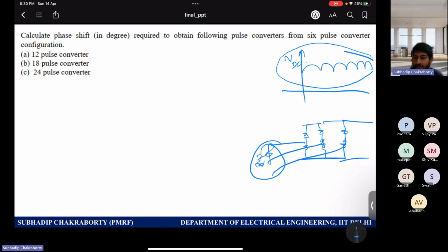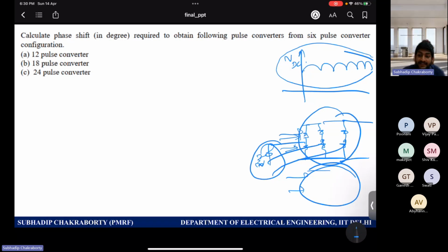So to improve the current quality at the AC side as well, if you use multiple such devices with some phase shift, you can tactfully cancel the harmonics. By Kirchhoff's current rule, some current harmonics may be rejected here and some there, by providing some phase shift arrangement. If you add those currents connected in parallel, your current quality will be more improved and closer to sinusoidal. If you provide two different phase-shifted excitations to these DBRs, or pulsed converters as I call them, your current quality at the AC side will be better. So both multi-pulse and multi-level converters are very useful at higher power or medium voltage levels, to improve current quality on the load side, since loads may be motors or other equipment.